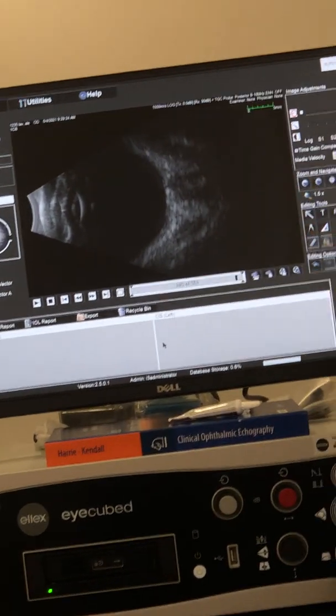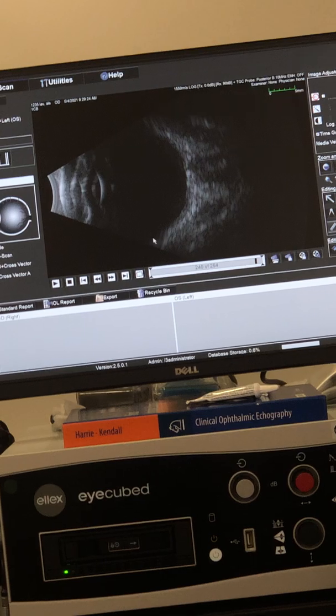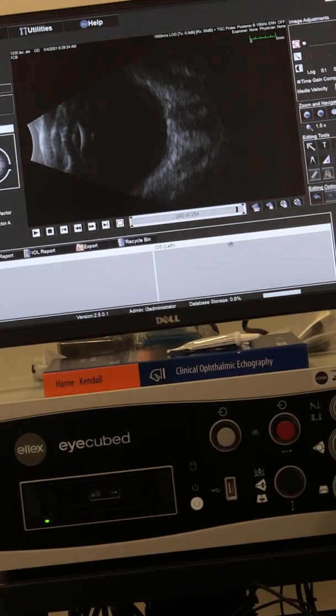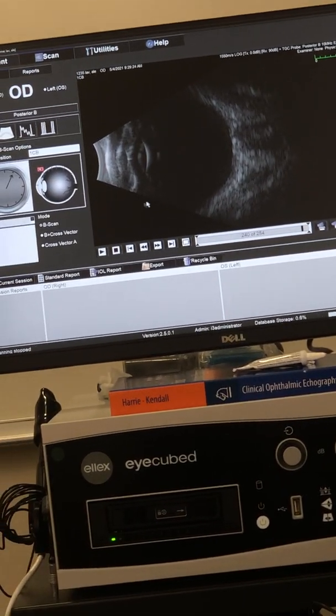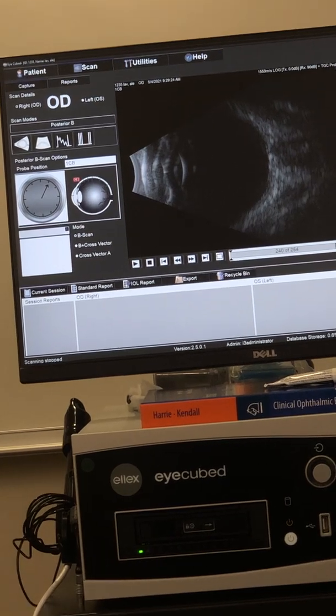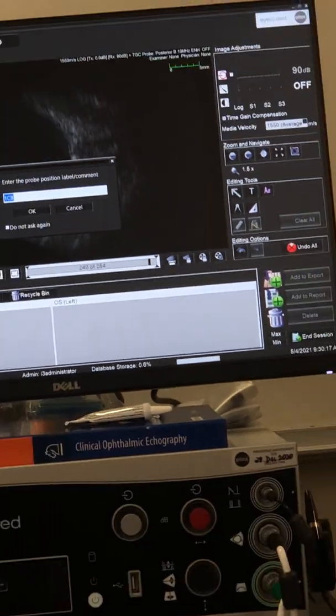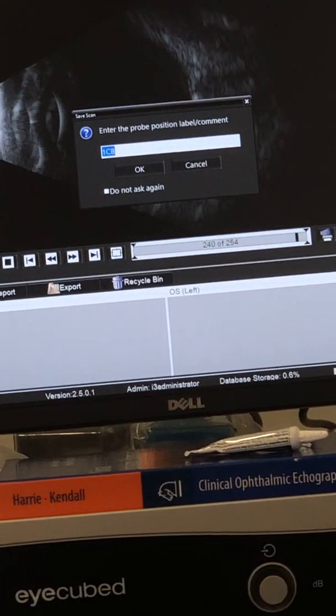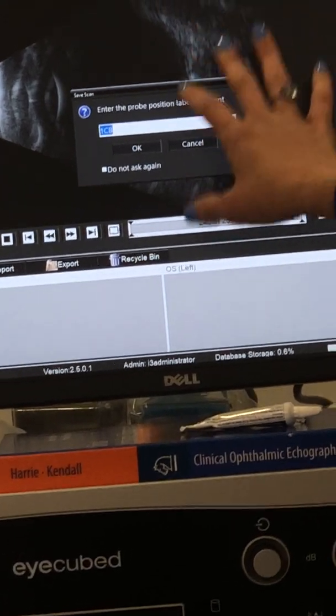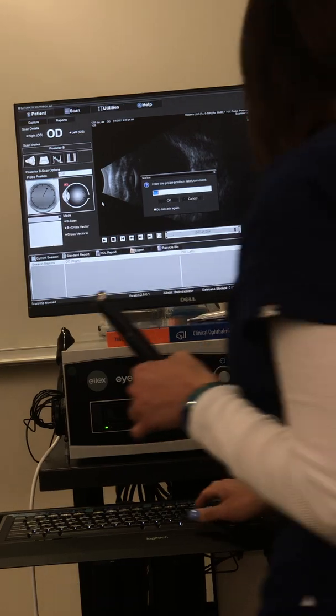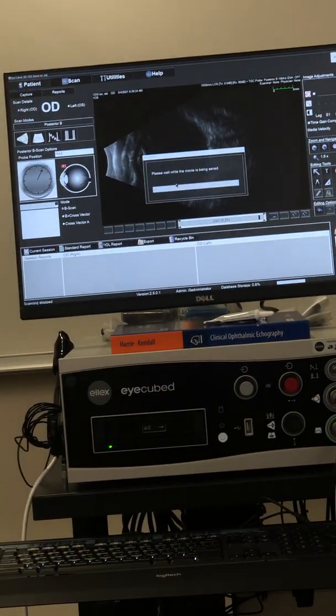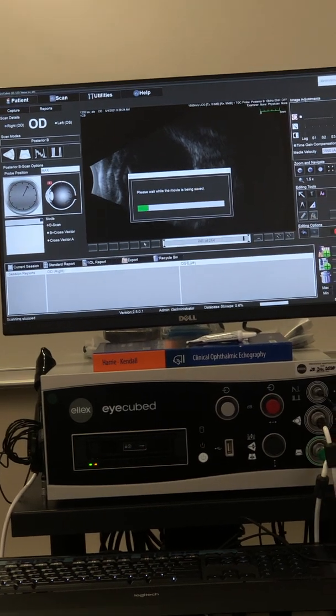So once you have your image here, if you want to save a movie, you've got to save it before you start that foot pedal again. So you're gonna click on the movie reel. And you can have this box come up if you like it. This is just a labeling box. So if you don't have a protocol in there, this will come up every time you go to save an image. So I can say my horizontal axial, and I'm gonna label that, and the movie will save.